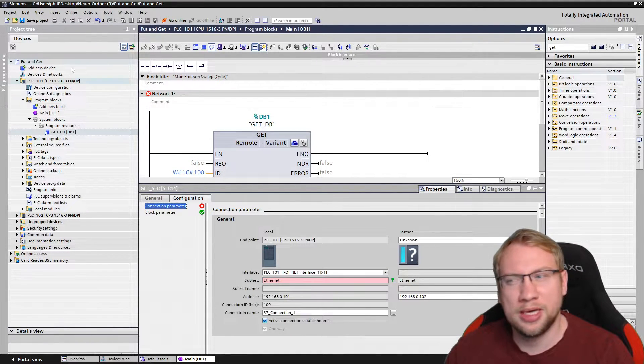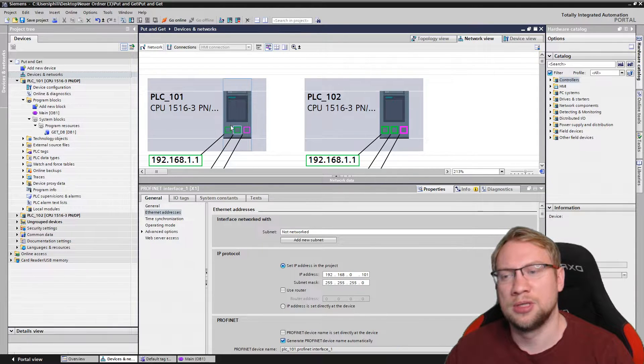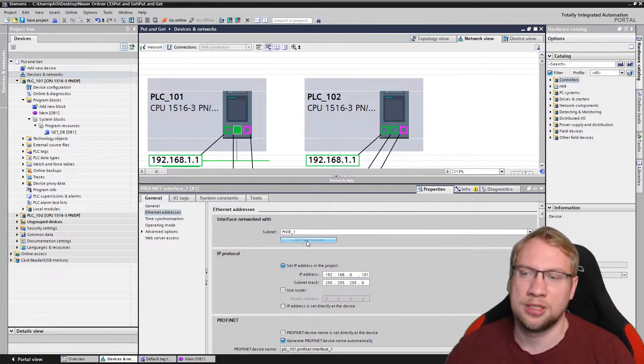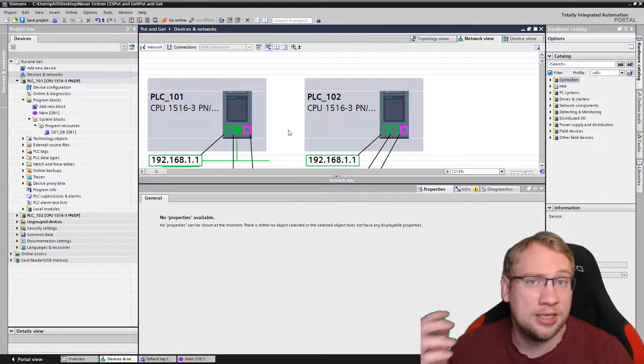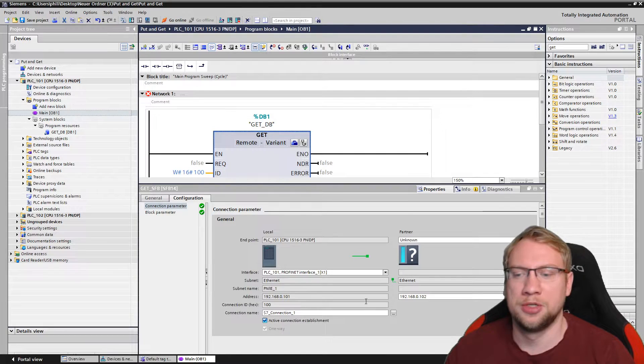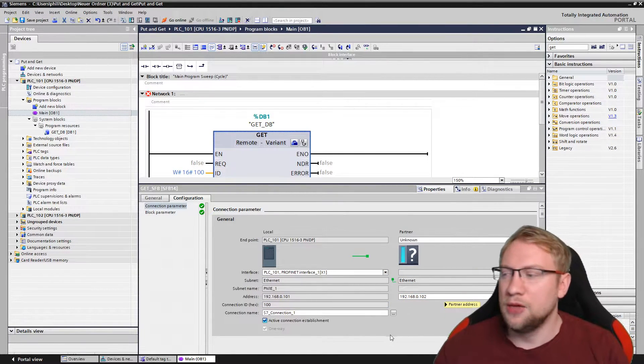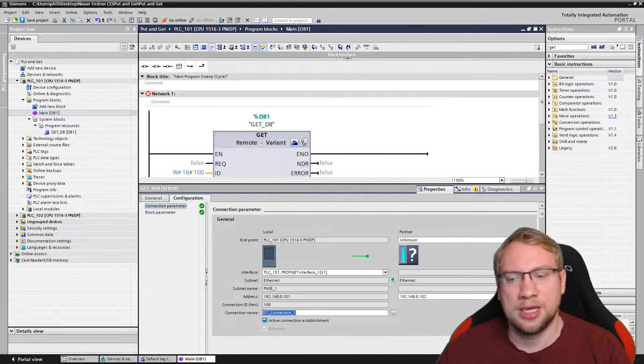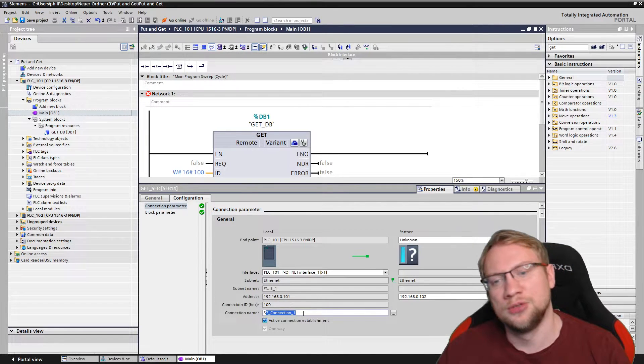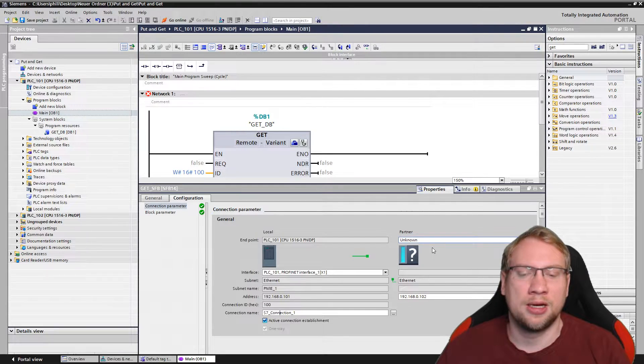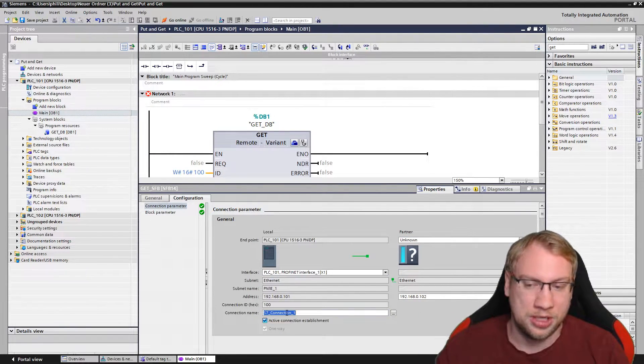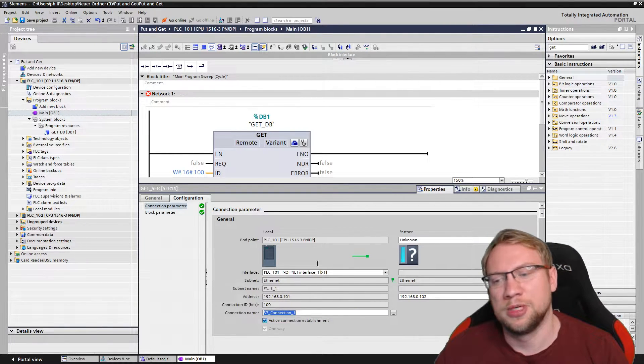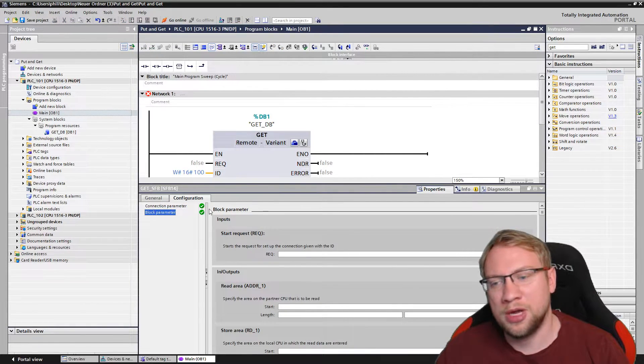My PLC is not yet on any network subnet, so I go to Device and Networks and add a new subnet so this PLC communicates on this interface. Once connected, everything should show green. If you already have a PUT or GET communication, you can reuse the same S7 connection since it identifies the same partner. A new connection is created automatically if you communicate to a different partner.